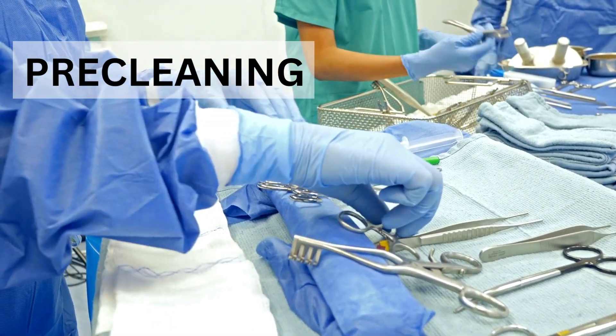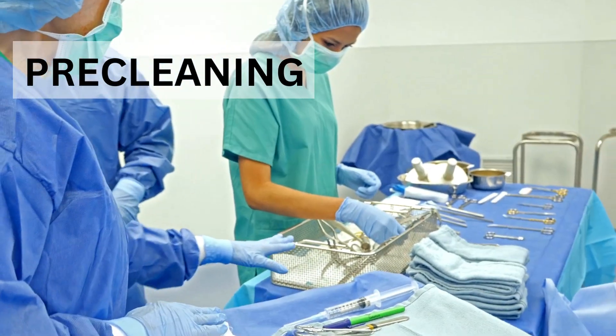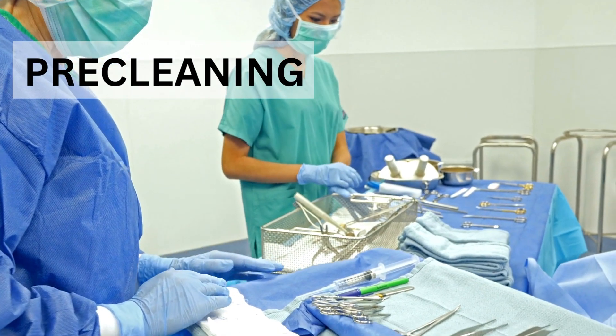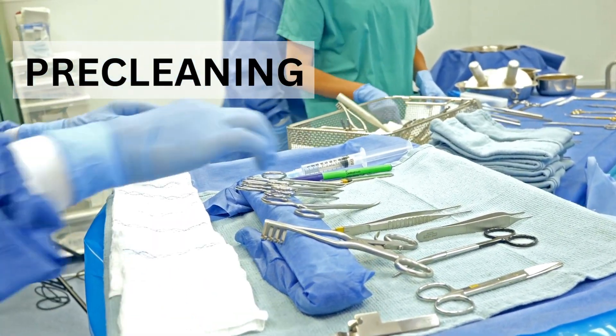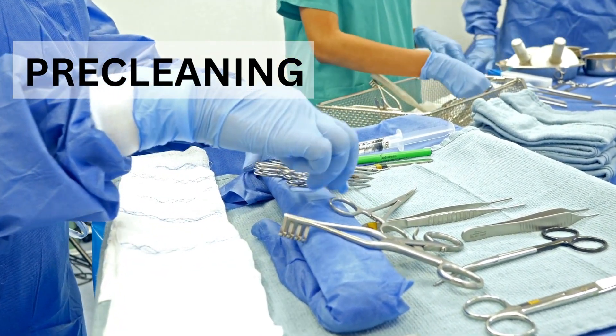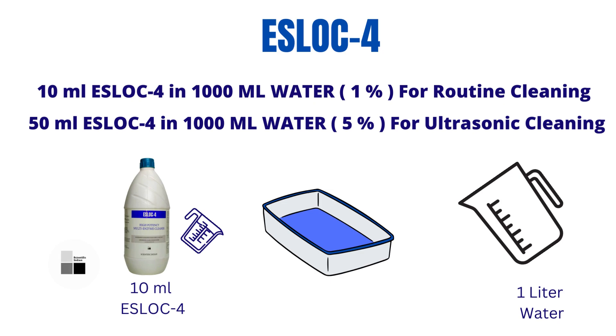The pre-cleaning process basically involves cleaning the laparoscopic instrument with water, followed by soaking the instruments in an enzymatic solution. There are multiple multi-enzyme cleaning solutions available in the market for cleaning these kinds of instruments. We recommend ESLOC-4 multi-enzyme cleaner for this job.